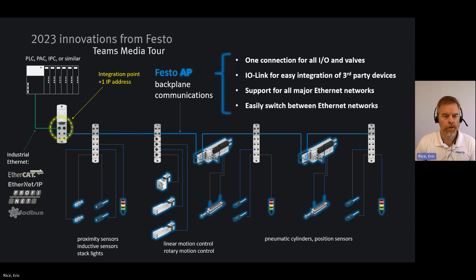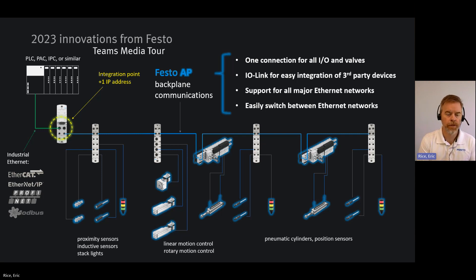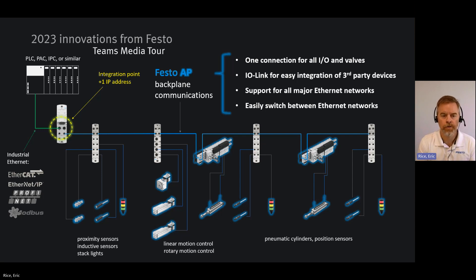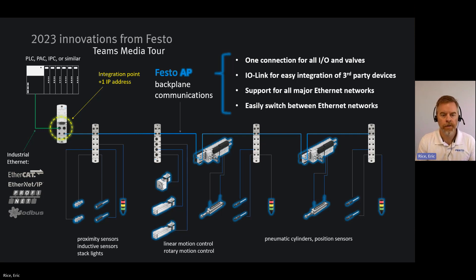We support all the major Ethernet networks and can easily switch between them. Think back to the diagram with all those yellow circles — each of those devices is an integration point, and each one has to speak the same protocol. If you're a machine builder building for a customer using EtherNet/IP today, all devices must speak EtherNet/IP. Next month, if you're building for a customer using PROFINET, you'd have to replace all those devices. With the Festo approach, the only thing you replace is the one bus interface device — everything below it remains the same. For OEM and specialty machine builders who must support multiple protocols, this ability to easily switch is a significant benefit.